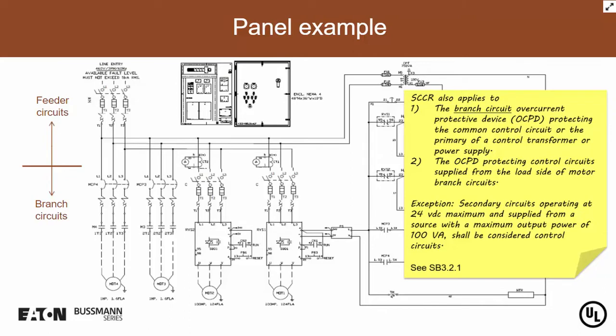All right, so let's look at a machine or an industrial control panel. And in general, every machine or industrial control panel looks alike to me. You guys make it do different things, but to me, you basically have power coming in. So you either have a main disconnect or main terminals coming into the panel or machine. Then you have power distribution feeding all of the branch circuits. So you have a main coming in and the power distribution throughout the panel itself, and then you have your branch circuits. And so we want to determine our SCCR based on all the components that we have on the machine itself, as well as in the industrial control panel.